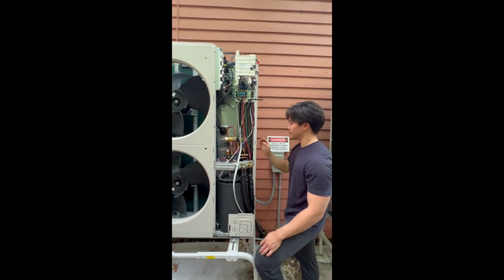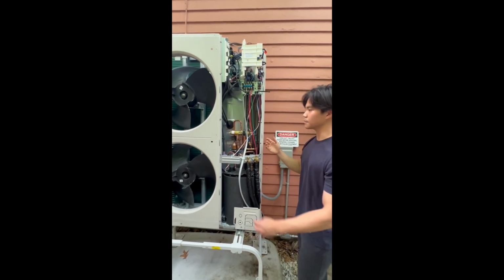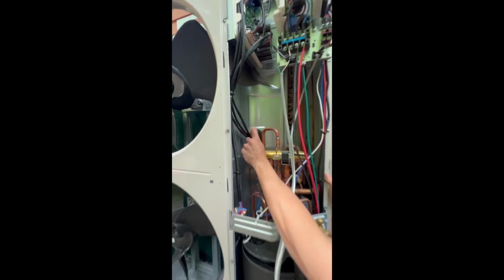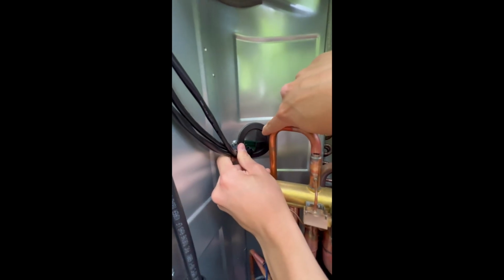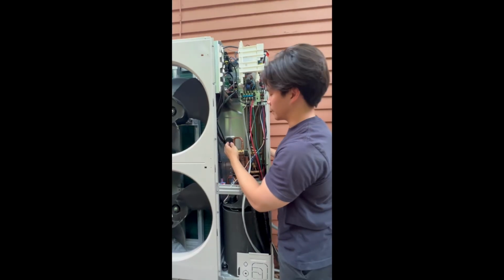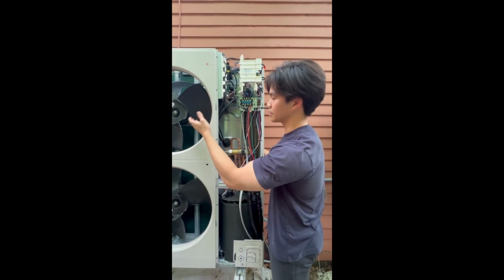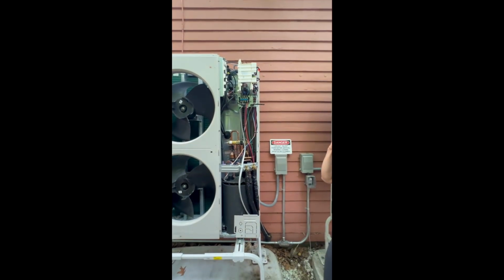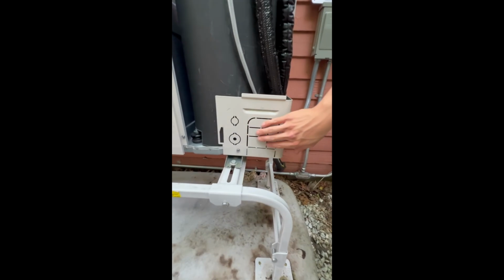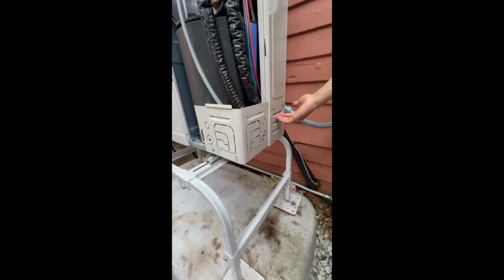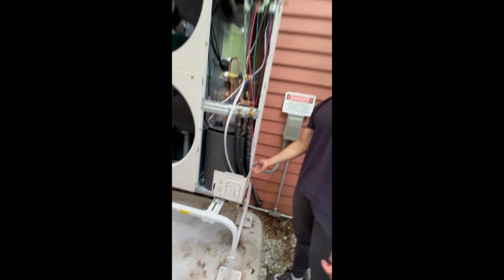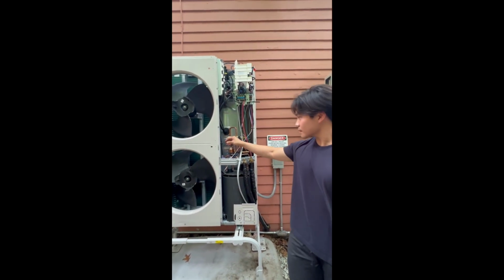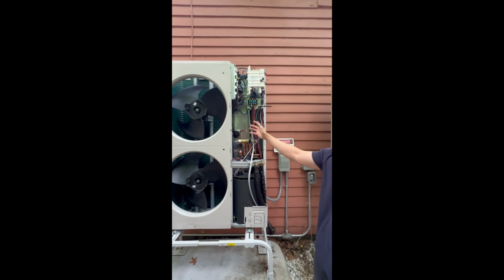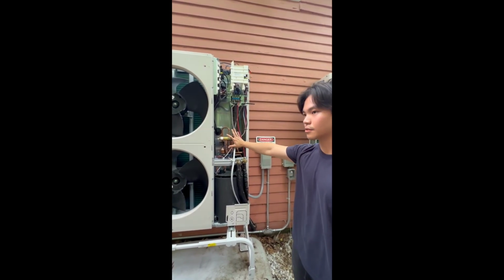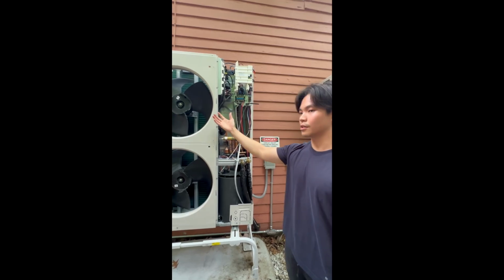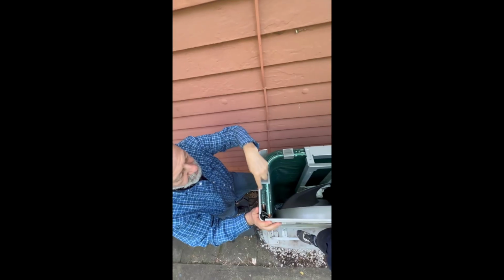In the control compartment, not a lot of air is supposed to flow through, but we have seen some places where it's possible to have some air bypass. It's like this one hole here. The air can simply be sucked through this hole into the fan section. That can come from these stamps, which the contractor can push out, like what Ian said, and these purposeful ventilation vents. Right. And all of these are going to add to the air bypass ratio, which may be purposeful to cool down the electronic section, or it might not be, and it will hurt the efficiency of the heat pump.